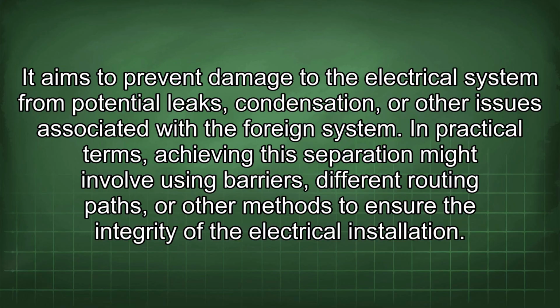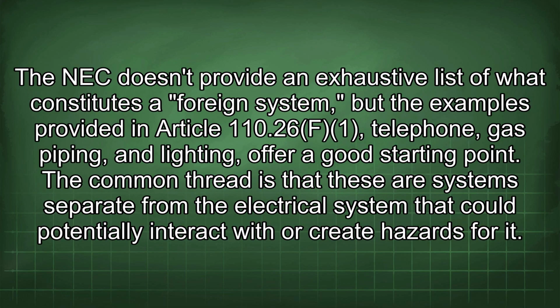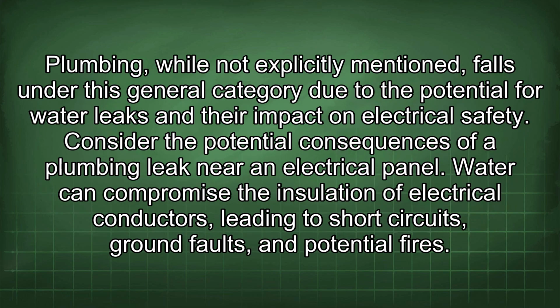The NEC doesn't provide an exhaustive list of what constitutes a foreign system, but the examples provided in Article 110.26(F)(1), telephone, gas piping, and lighting, offer a good starting point. The common thread is that these are systems separate from the electrical system that could potentially interact with or create hazards for it. Plumbing, while not explicitly mentioned, falls under this general category due to the potential for water leaks and their impact on electrical safety.